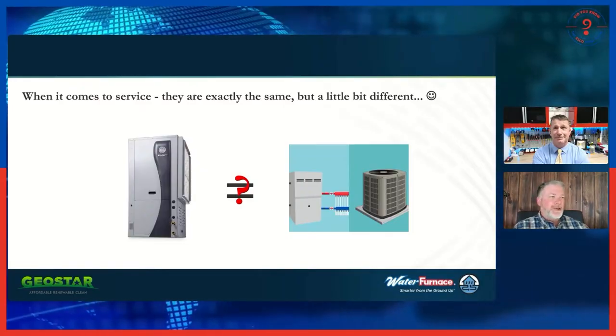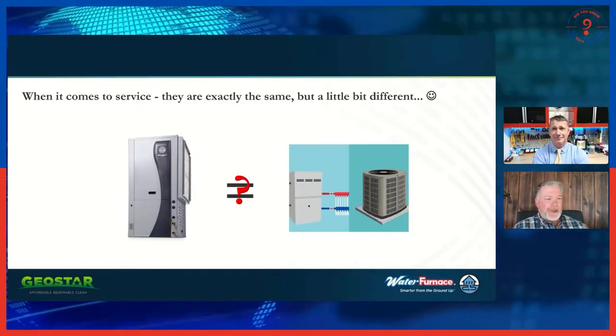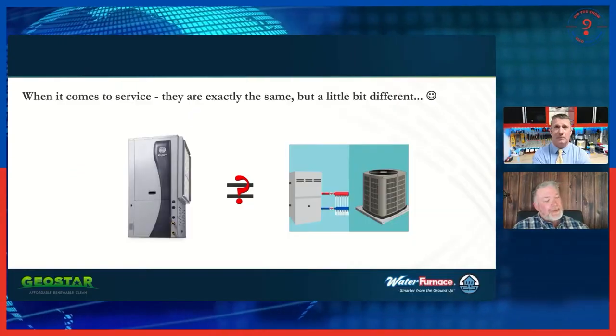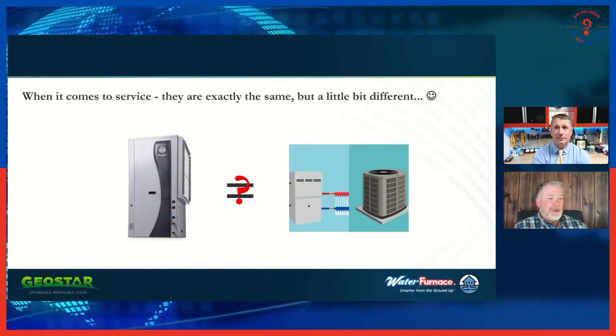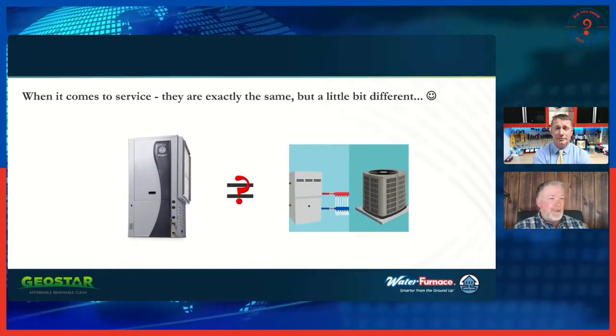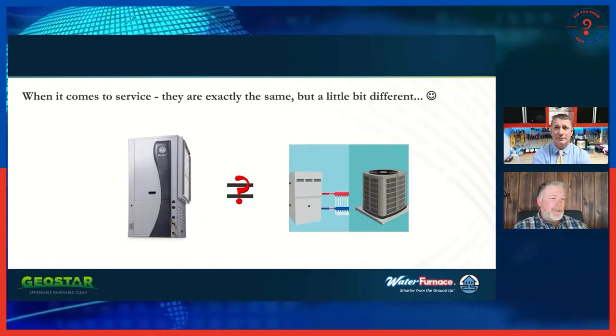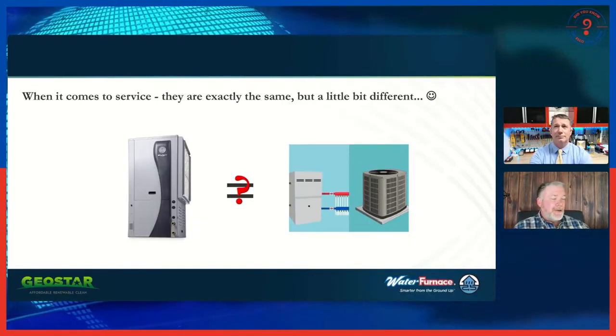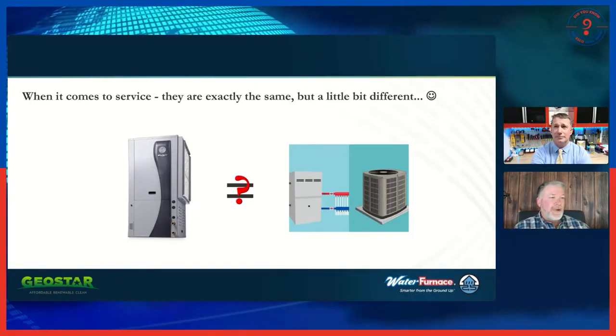You go out to an air conditioner and it's got a low pressure situation. They say, well, it could be low on charge. I'm like, well, yeah, that could be. Could have a bad low pressure switch, that's possible. Could have some wiring issues, that's possible. But generally speaking, low pressure is caused by lack of flow across the evaporator.